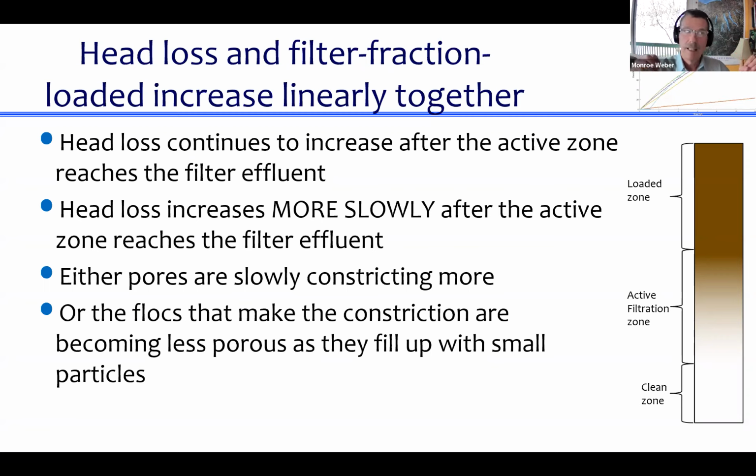So maybe it takes a minute for one of those pores to fill up. Then in 2 minutes, 2 of those pores are filled up. And in 3 minutes, 3 of those pores are filled up. And as you're coming down through the filter, by the time you get to 5 minutes, you've got to go through 5 of those clogged pores, and you've got the head loss of 5 of those pores to deal with. Did that make sense? So head loss increases linearly with time because the number of formed and fully constricted pores is increasing linearly with time.